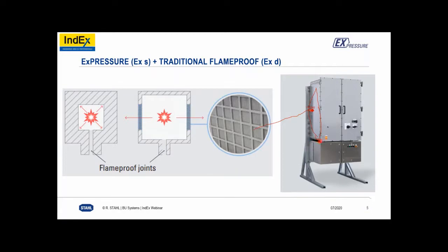The traditional flame paths are on the cover and on the bottom side of the enclosure, where all the cable entries or the conductor bushings go through, either through the Ex e connection chamber or, in case of direct entry, through the barrier glands. These two sides, the cover and the bottom side of the enclosure, are according to the EXD type of protection. But the sides and the top of the enclosure are EXS, and this is combined together in one cabinet.